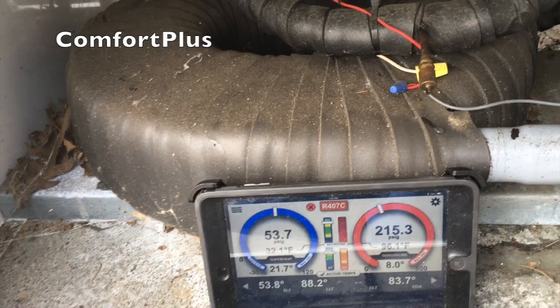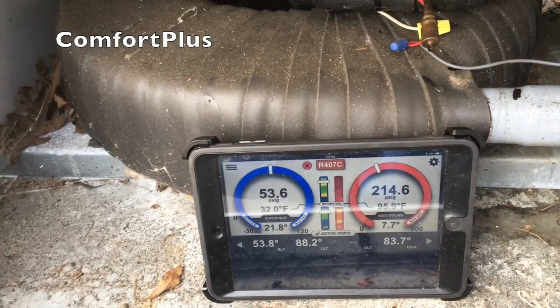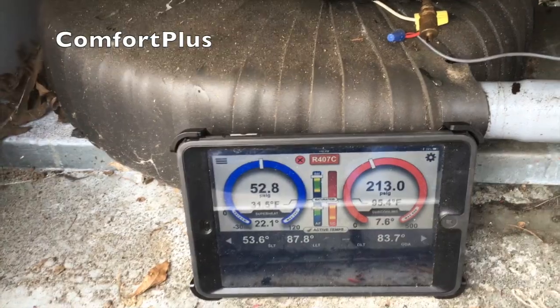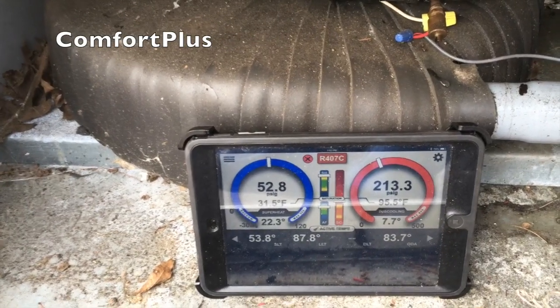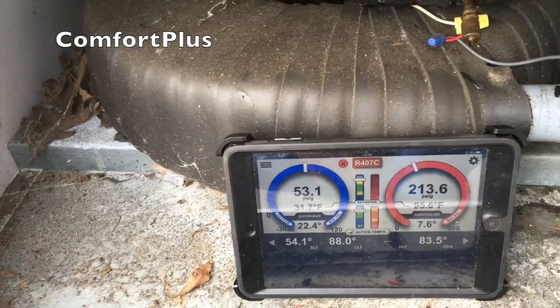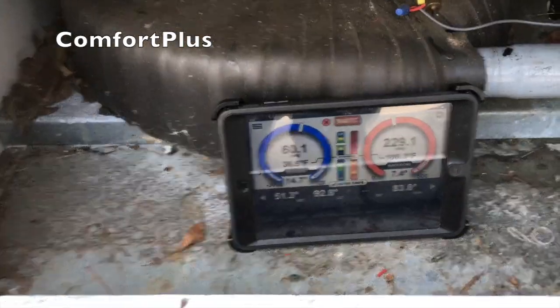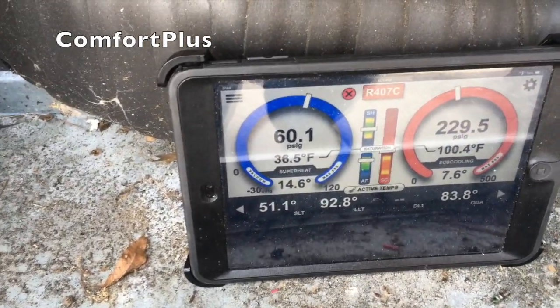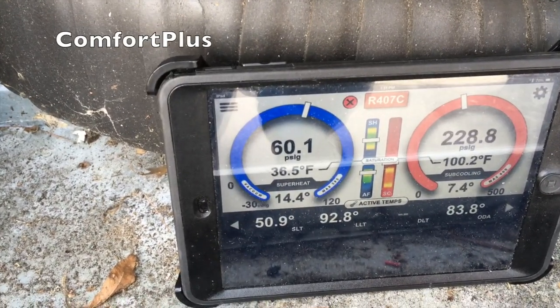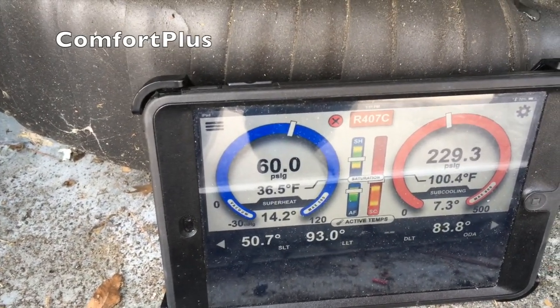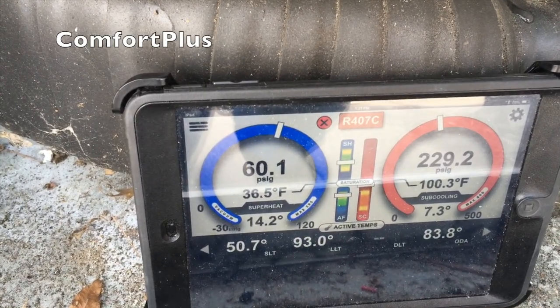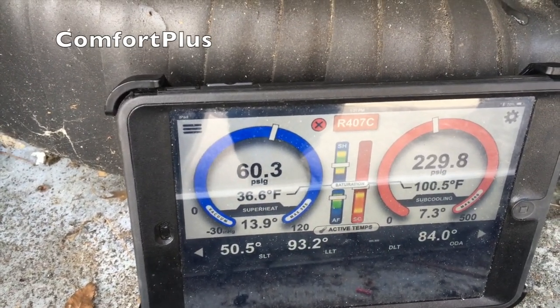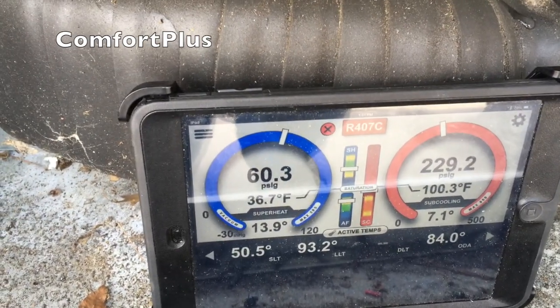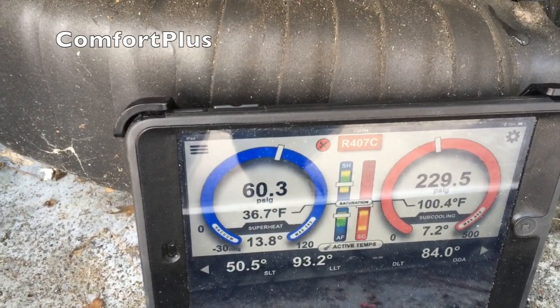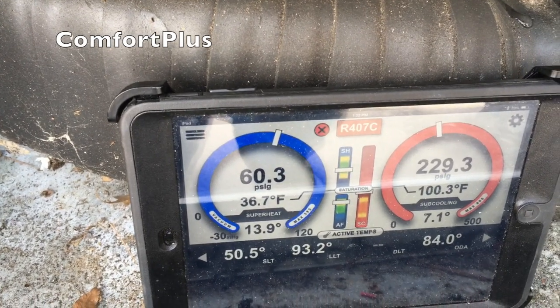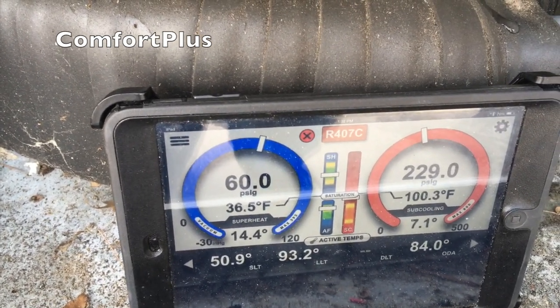He said it's getting a lot colder than it used to, even though the set point was the same. The water was getting colder inside, so I'm going to let this thing settle in and work between its set points and see where the superheat stays. The dry cleaning unit is at its highest heat cycle right now. It's 160 degrees, and this water is going to be cooling it off. So it's got the temperature of the return water over 70 degrees now, and we're holding about 56, 57 degrees on our outlet with a 14-degree superheat and 7-degree subcool.